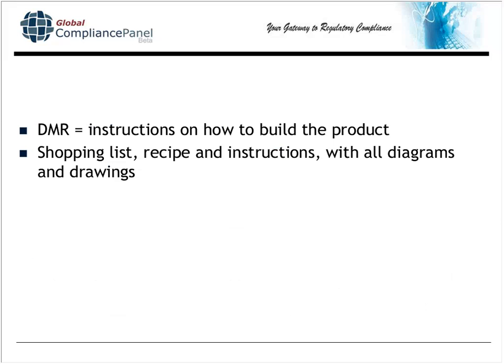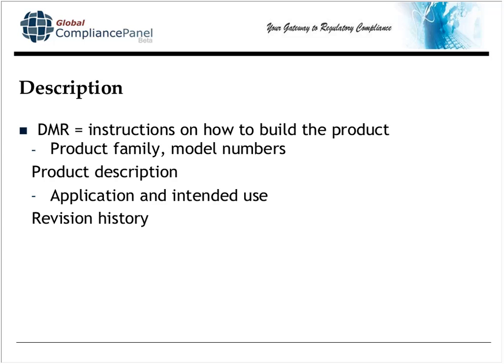Moving now to the DMR. The DMR is instructions on how to build your thing. A better way to look at it is if you're making a cake: you have the shopping list, which is the parts you need; the recipe and instructions, which is how to make it; and since the device isn't really a cake, you're going to have things like diagrams and drawings to assist in manufacture.